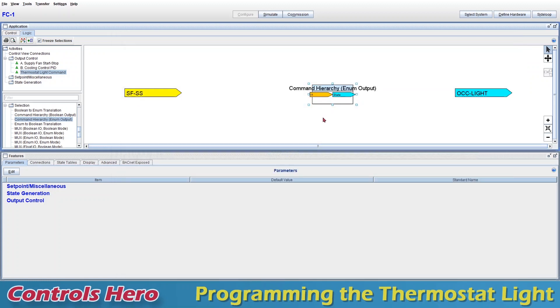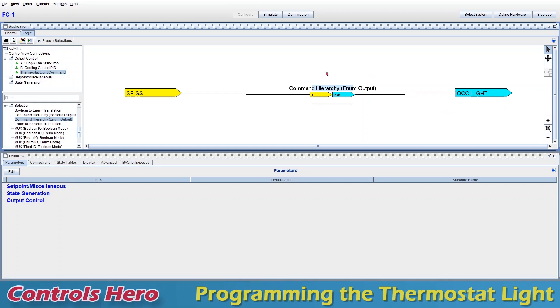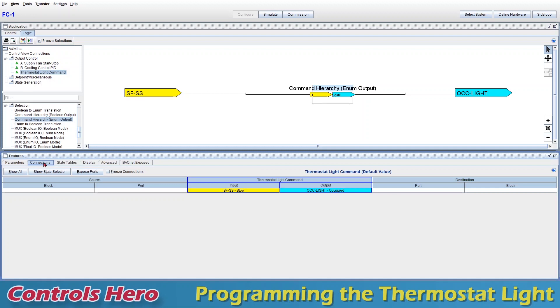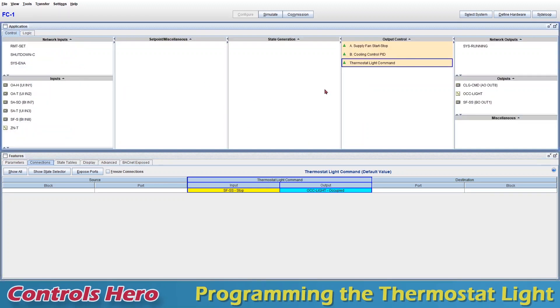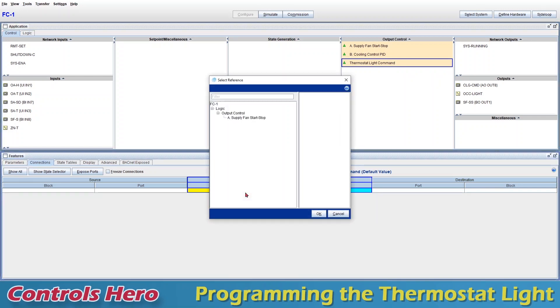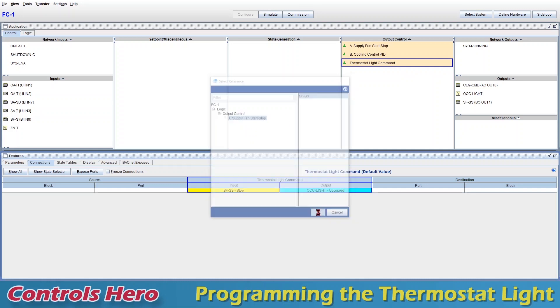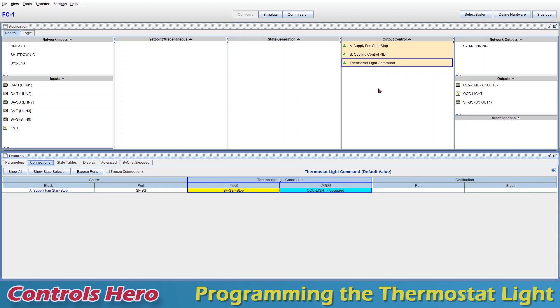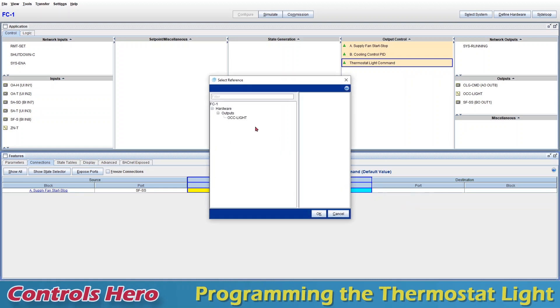Now let's start making connections. I can connect my supply fan start stop input to my command hierarchy, and then to my occupancy light, and this piece of logic is done. Now I go to connections, and I got to connect the actual supply fan and occupancy light. I can do it from here and just go to control. Here's my new module. So it's supply fan start stop input, I'll connect it to the supply fan start stop right here. Only choice, easy, okay. Then my occupancy light to my actual point, thermostat point. So right click on it, make connection, only choice, input one, okay. And there you go.